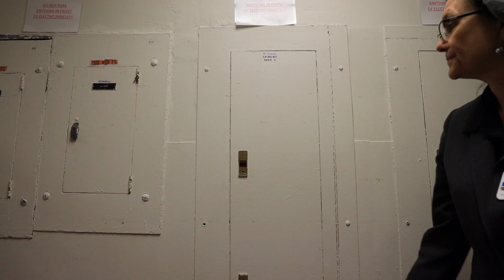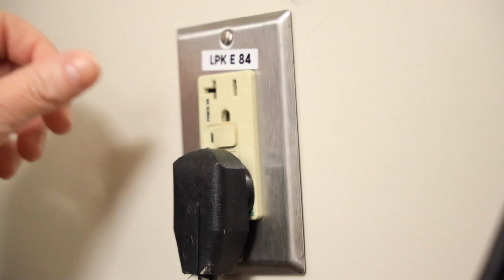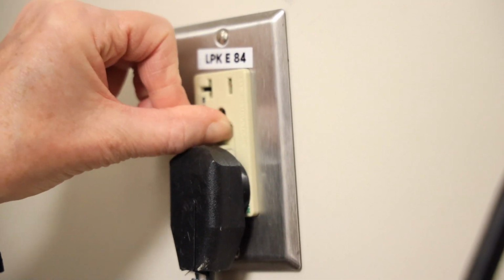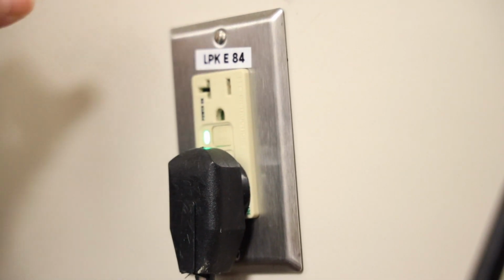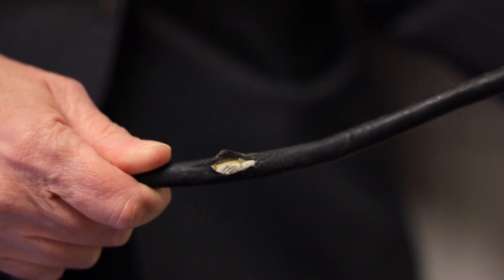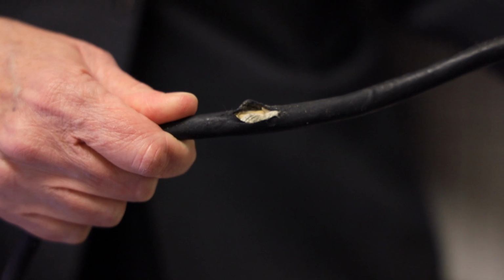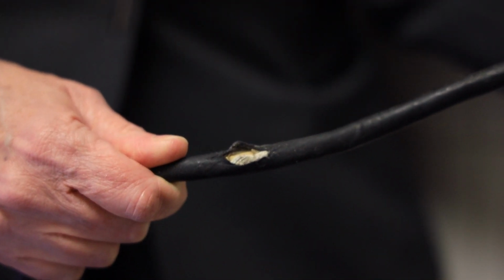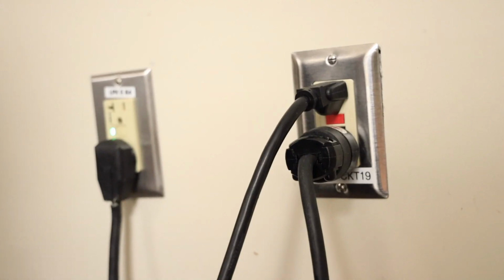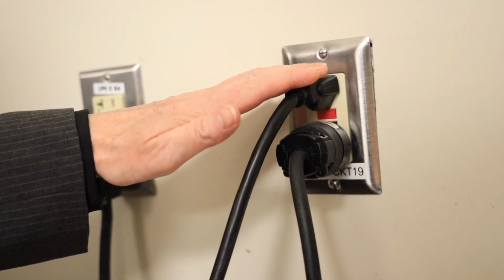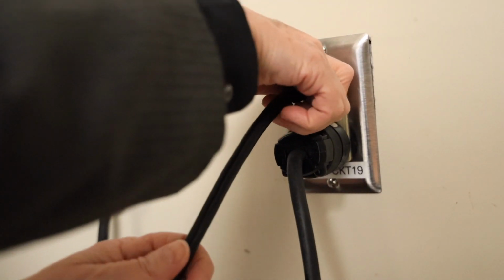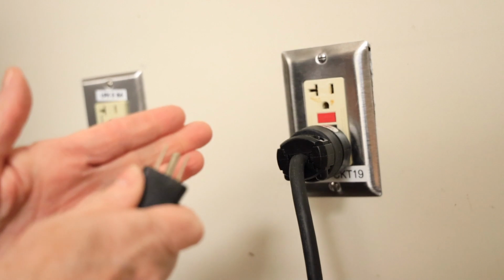The clues one could look for regarding electrical hazards are tripped circuit breakers or blown fuses, damaged electrical wires, cords, connections, or junction boxes. Ground fault circuit interrupters that keep tripping off and need to be re-tripped. Worn or frayed insulation around wire or connection. Cracked casing on double insulated equipment. Sparking or overheating. Sparks from an electrical tool or an electrostatic discharge can ignite flammable materials in the area.